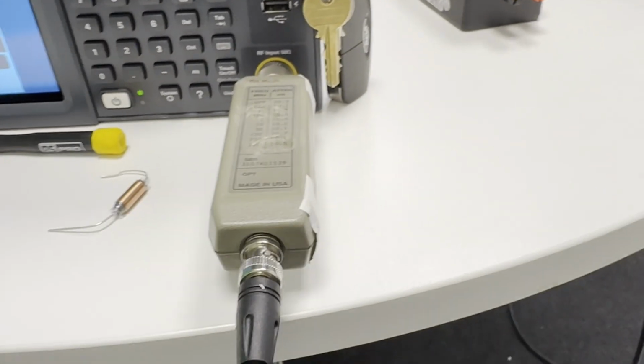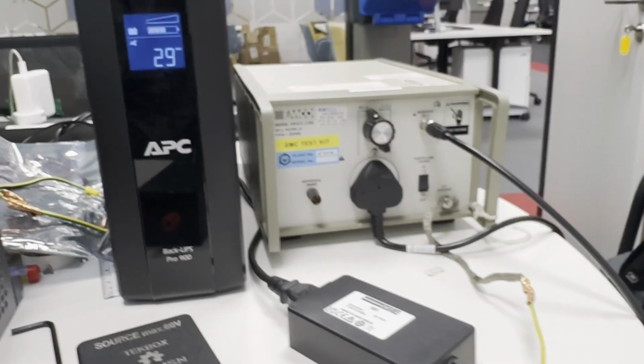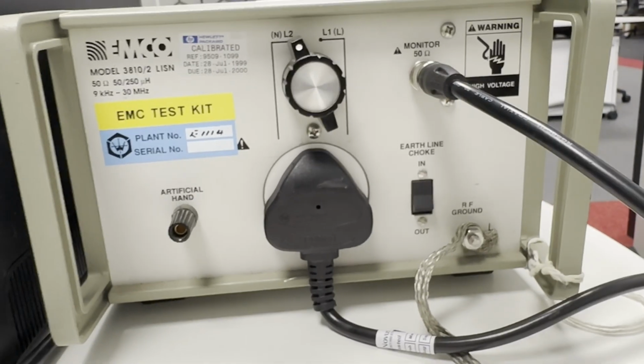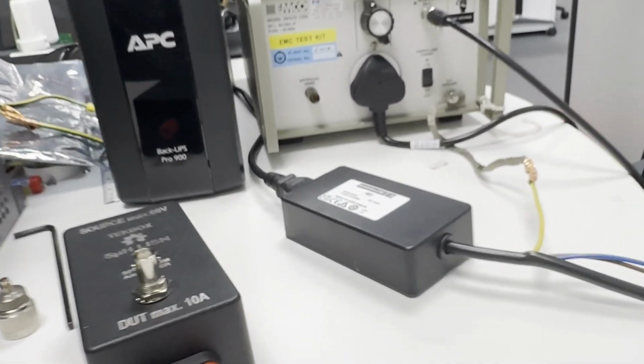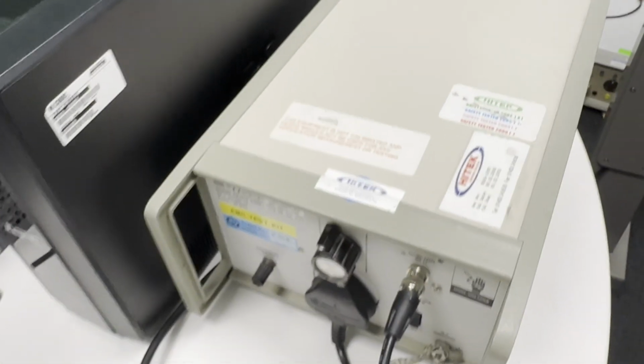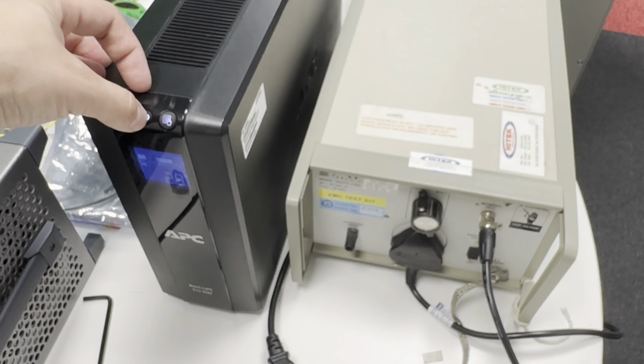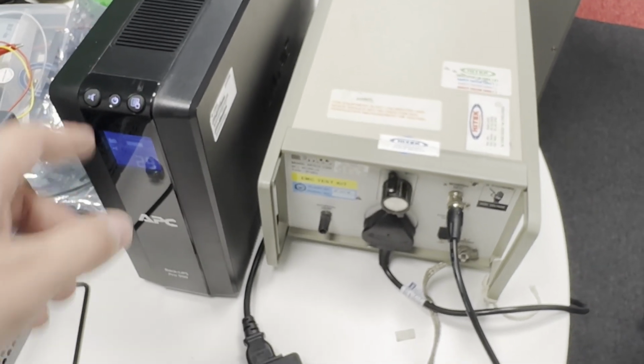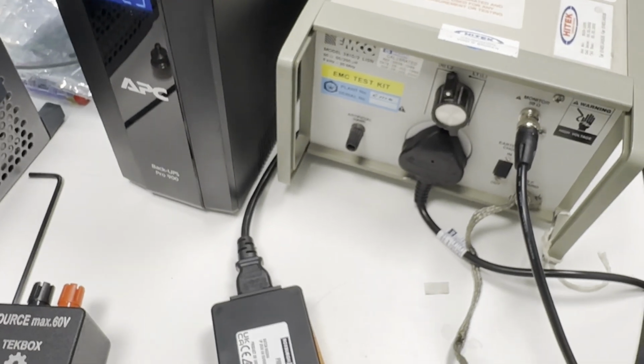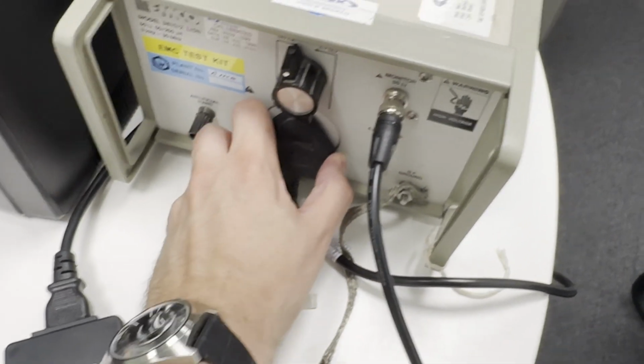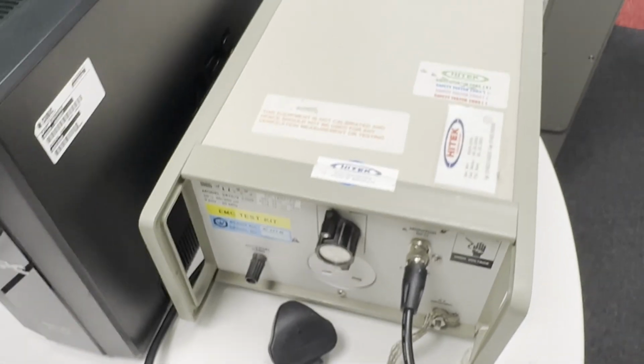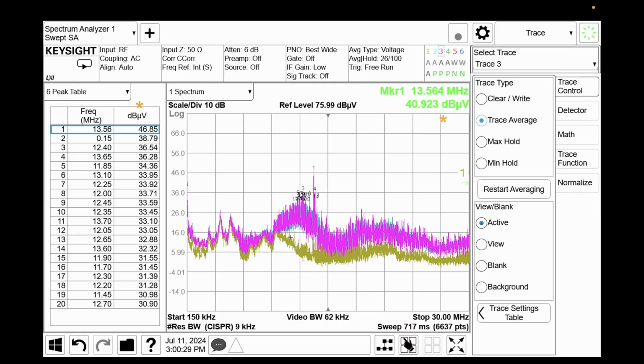Then the final thing to say is that when you've done the measurements, when the measurements are complete with the LISN, you should disconnect it first before powering off and disconnecting the mains from the LISN, because when you disconnect the LISN from mains, it can discharge into the Spectrum Analyser and damage it. There you go. And here's the screenshot of the final measurement that I took in this setup.